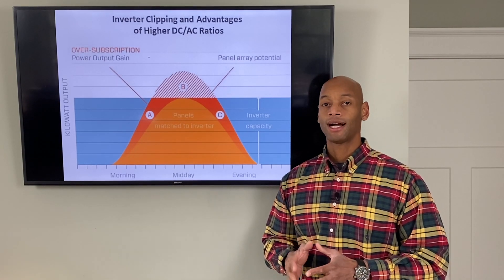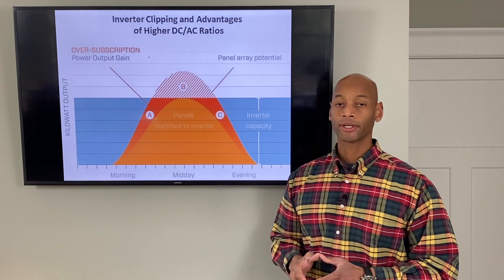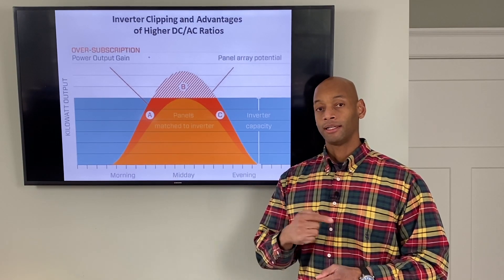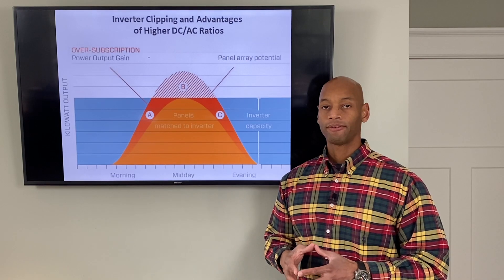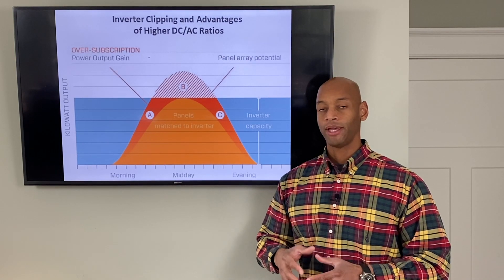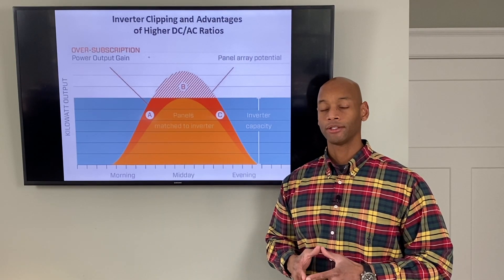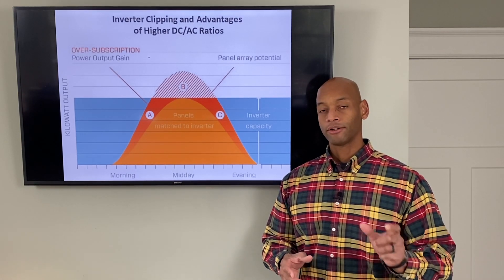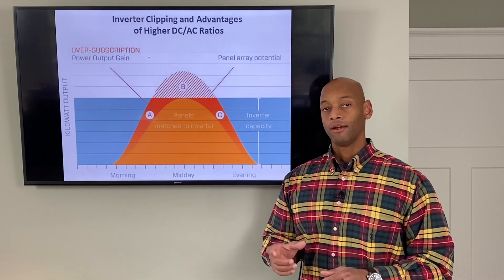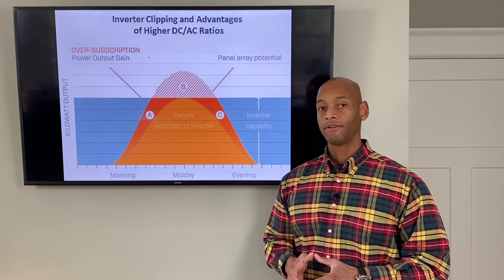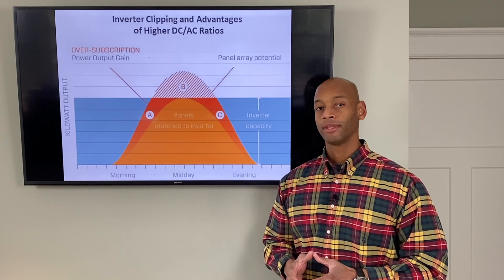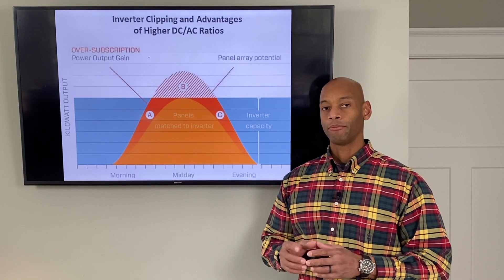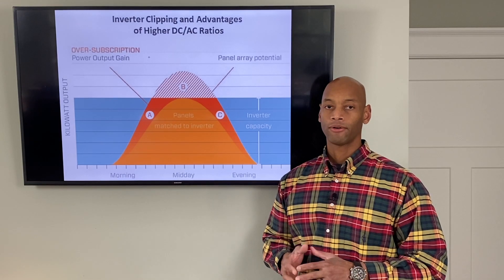This is very, very common. The solar panel we've installed most, at least leading up to this year, was a 325-watt Canadian Solar panel — you may have seen our previous video about that panel. We would pair that 325-watt solar panel with a micro inverter rated for 250 watts output power. So again, the difference between those two numbers is essentially the clipping factor or clipping loss.